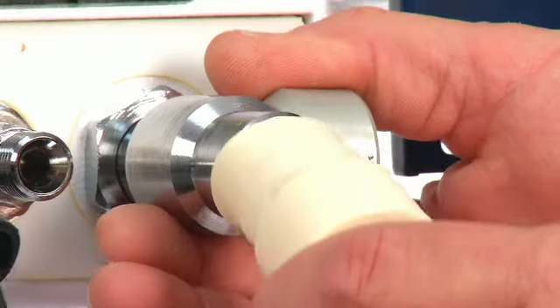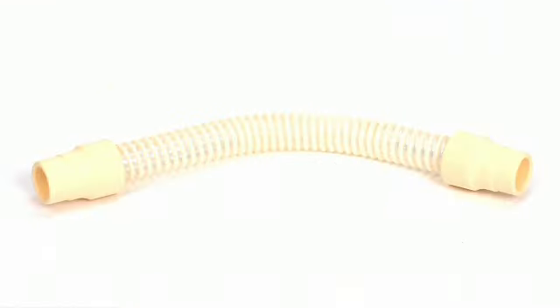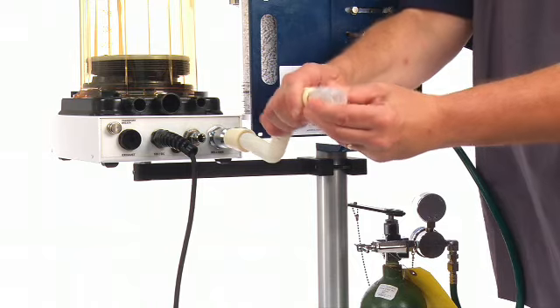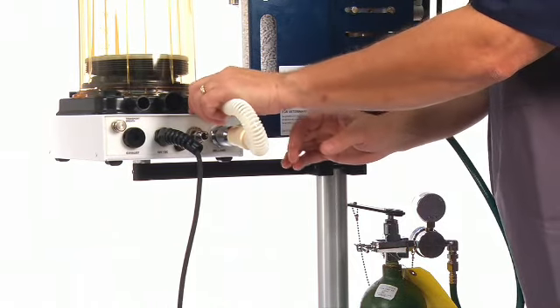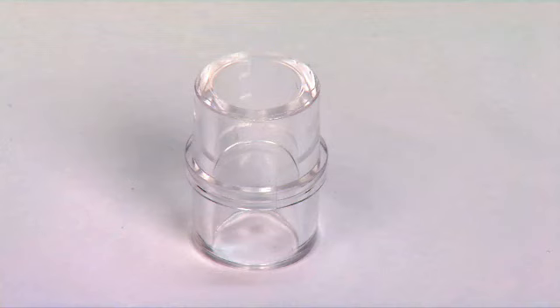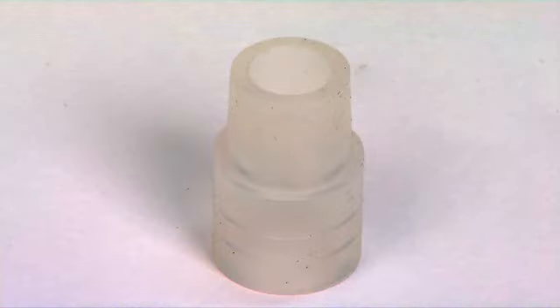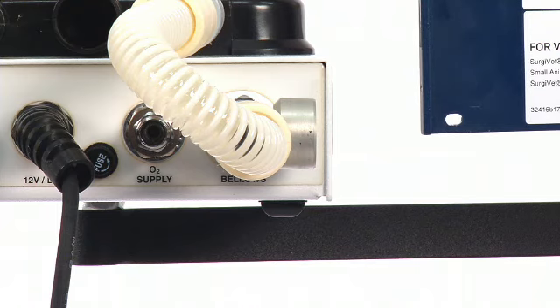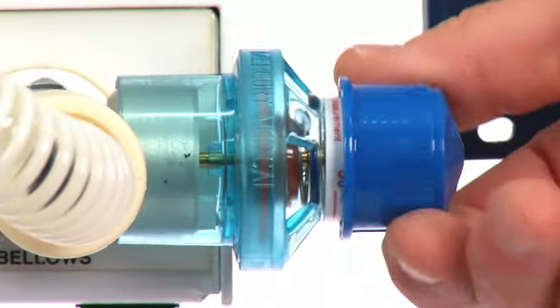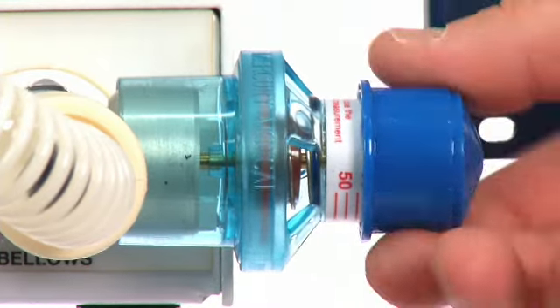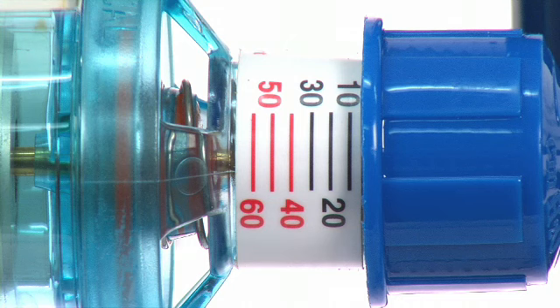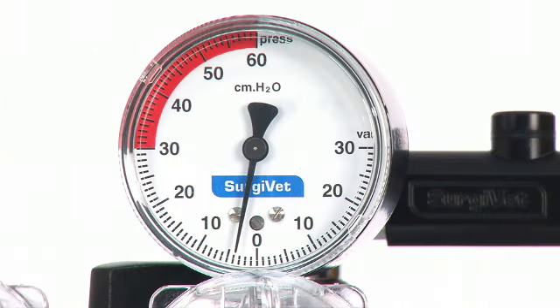The drive gas supply port accepts one end of the short 12-inch cuffed hose and connects to the drive gas inlet on the bellows base, utilizing the 22 by 22 mm plastic adapter and 22 by 17 mm silicone adapter. The pressure relief valve connects to the drive gas supply port. The numbers on this relief valve can be used as a reference, but true circuit pressures are determined by the manometer located on the anesthesia machine.